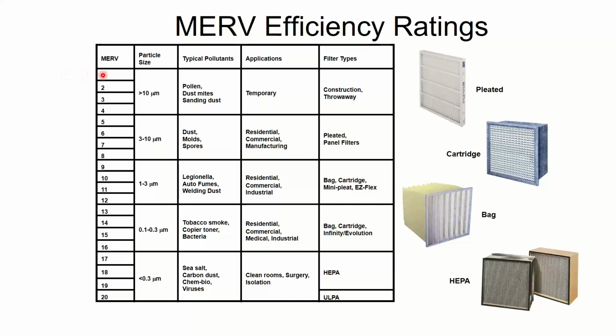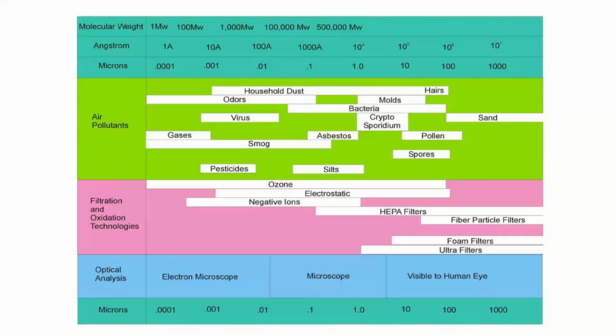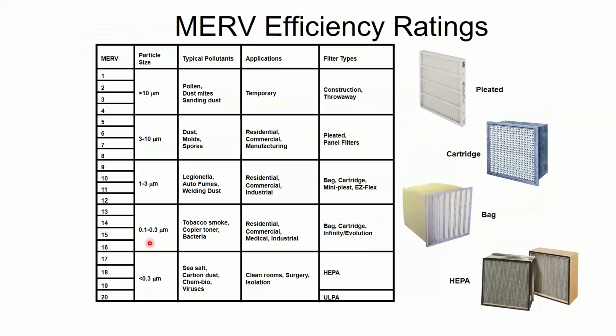1 meaning it's the crappiest filter. It's basically my t-shirt. Like it's almost nothing, right? And then 16 being the high end of the scale. And then the size of particles that we can catch with that. If I go back to my particle sizes, right? Let's say I want to catch, well, let's do COVID because that's probably what you care about right now. What we said was 0.125 was the micron size right here. So for 0.125, I need to be down here. I'd have to get a little bit finer detailed chart, but it's going to be like a MERV 13 or 14 that I'm going to need to catch something that small.